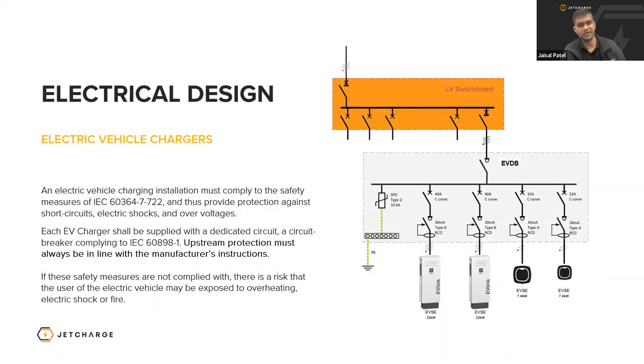Electric vehicle charger designs are done in a wide variety of ways. This is just one of the ways, where you have an LV switchboard feeding the distribution board, feeding EV chargers, and then you have dedicated circuits to each EV charger. An electric vehicle charging station typically complies with the safety measures of IEC 60364-7-722, which is a bit of a mouthful, and provides protection against short circuits, electric shocks, and overvoltages, where each charger will be provided with a dedicated circuit breaker.